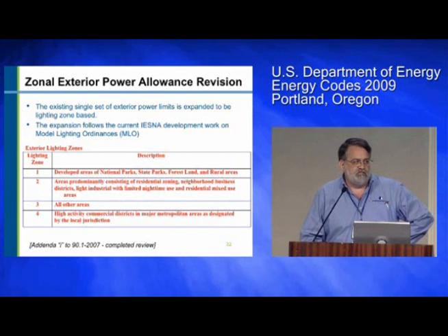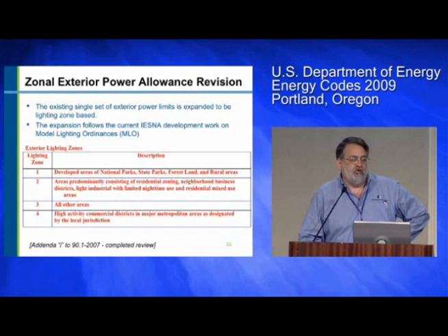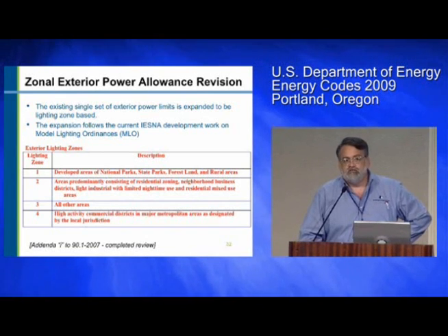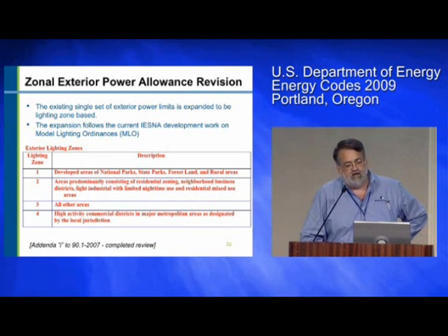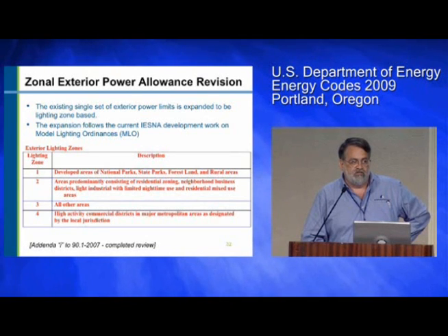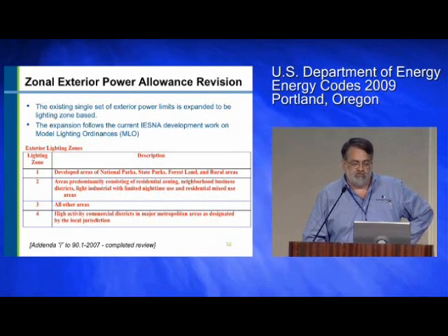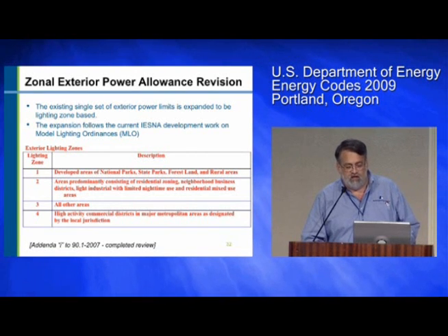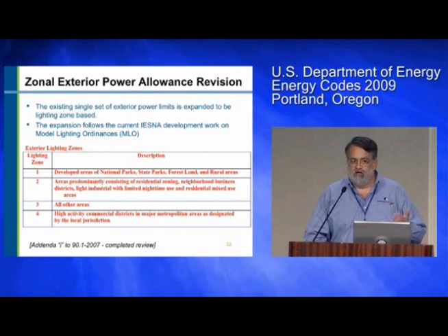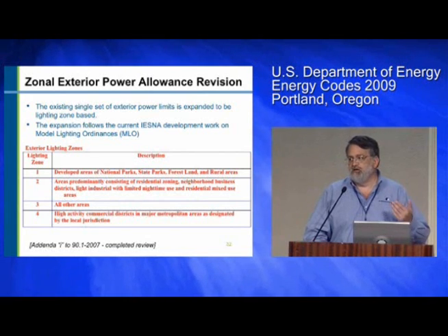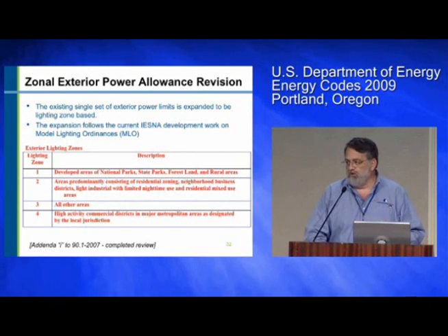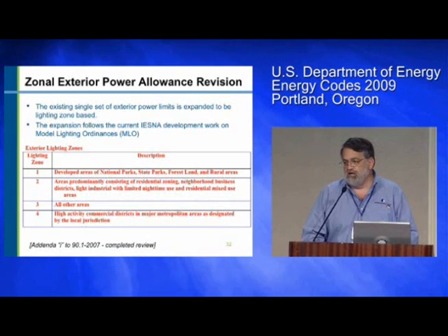The model lighting ordinance and other efforts have been going on for quite a while to define exterior lighting zones. Some zones you just don't need very much light. Some zones you need more. And so there is a document that's floating around that's going to define these for jurisdictions. And what the 90.1 subcommittee did is looked at these definitions, crafted definitions that a building official could probably hang their hat on and actually apply, and then looked at the lighting requirements based on that, because the previous set of exterior requirements was based on any zone, the highest zone possible. Of course, zones that don't need as much light would be wasting it.